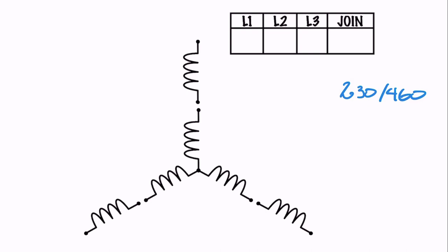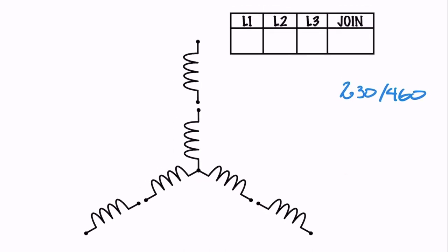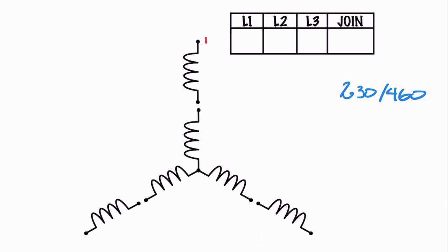The first step is to number our leads. The convention I was taught and that I teach: we start at the top, that's number one, and then we work counterclockwise — so two there, three there. Then we do the spiral method, working inward: four, five, six, seven, eight, nine. We also have leads 10, 11, and 12, but they're all internally connected to the star point, so we don't really count them. Just know they exist and are connected — that's what makes this a Y configuration.